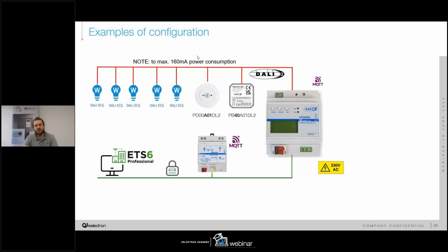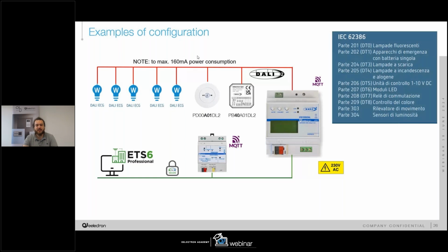Here in this example, we can see also how over the KNX bus, we can power it with our KNX bridge. That is a power supply plus IP interface that enables you also MQTT. Again, MQTT, so meaning that if we have to integrate an MQTT broker, we can easily forward all the information about DALI directly from the DALI gateway, and the rest of the information of the KNX system directly from the bridge. Here we can see some note about every part that now is compatible with our gateway.